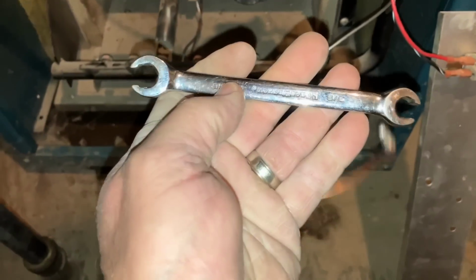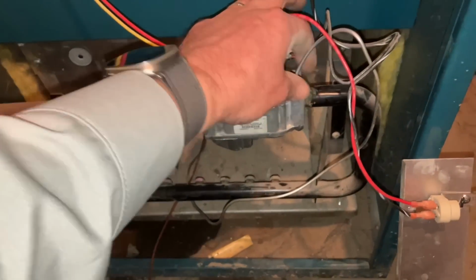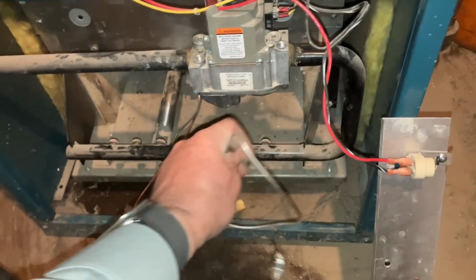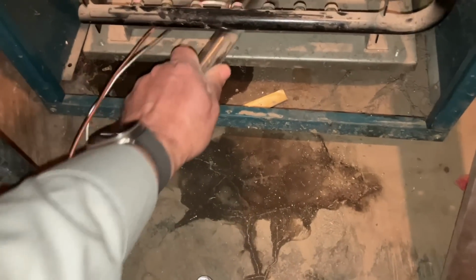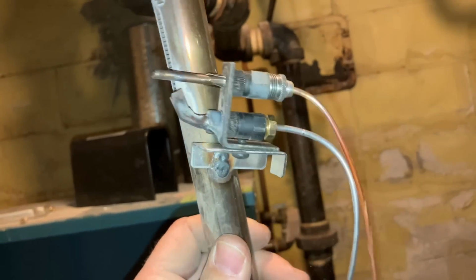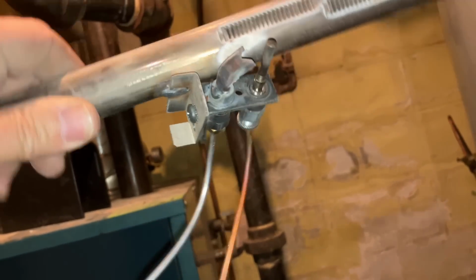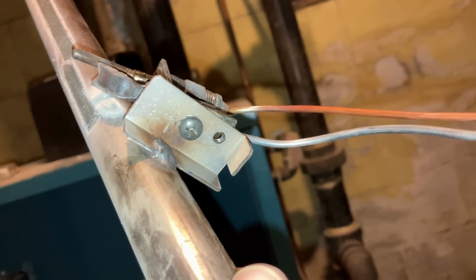All right, now we just have that one, using this box wrench. Link in the description box down below, of course. Okay, so there is that. Homeowner said he just replaced the thermocouple. Yeah, you could tell a homeowner put that in. Missing one of the screws holding on the pilot burner assembly, but other than that, it's not going anywhere unless the screw's in there, which it's not. But we've got to get the vacuum and vacuum all that stuff out of there. All right, I vacuumed everything out of the bottom of the combustion chamber. Nice and clean.